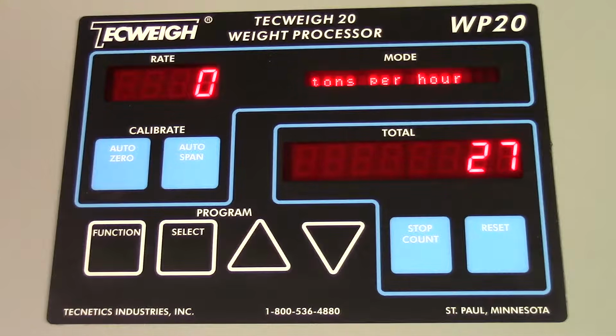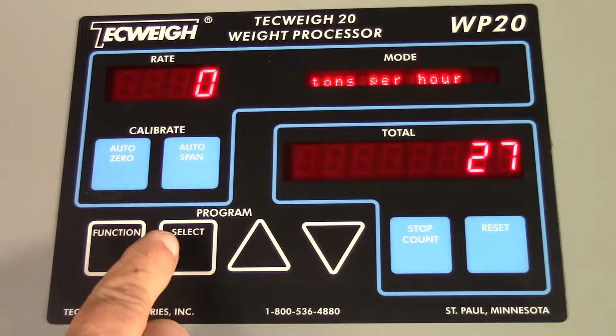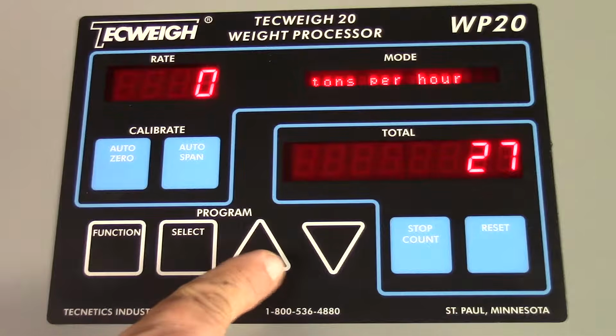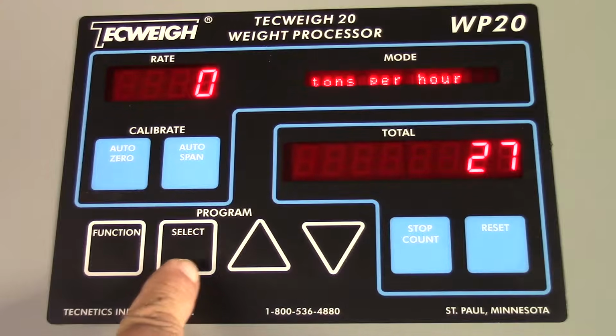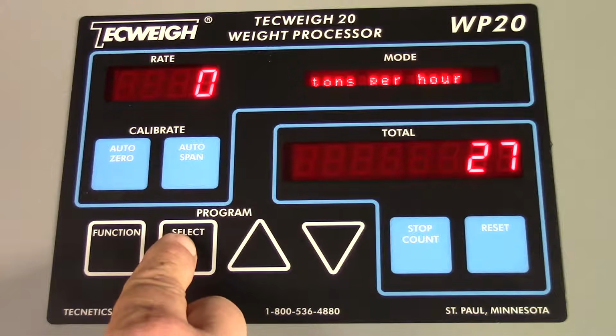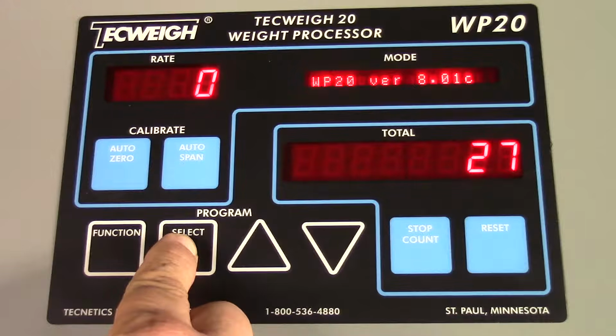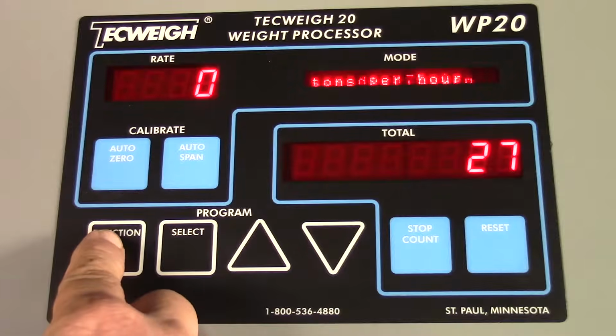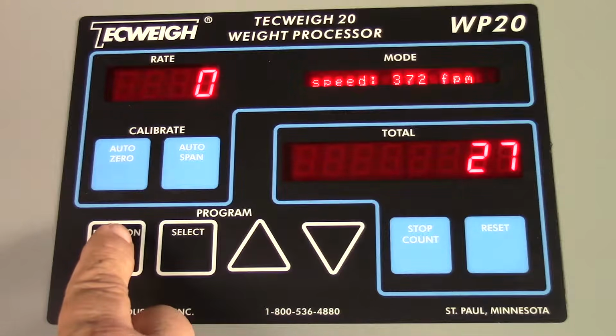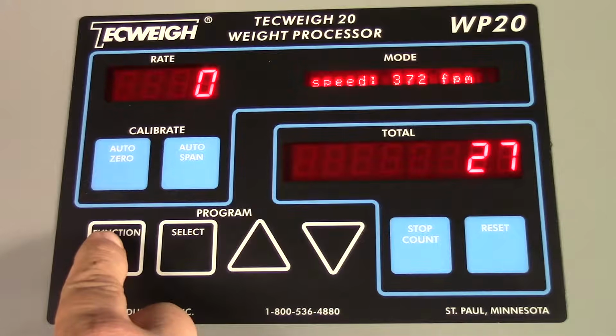So now let's take a look at the WP20 electronics. We have a couple of buttons: auto zero, auto span, up and down arrow, the select button, stop count, reset, and so forth. If we hit the select button, it's going to show us the version of software. If we hold down the function key, it'll show us the speed, but if we hold it for 5 seconds, it will go into program mode.